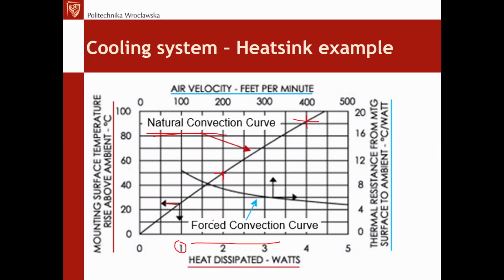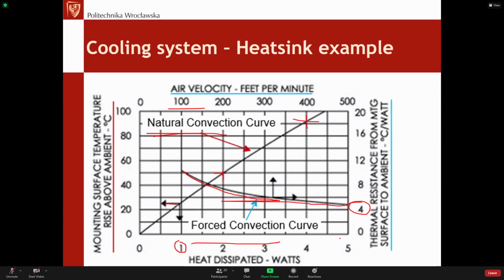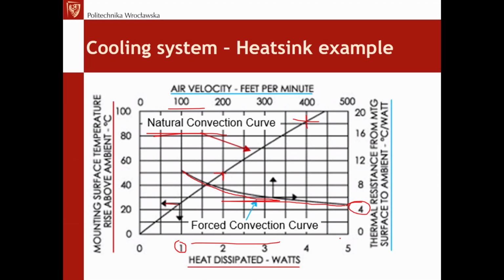In the case of forced convection, adding a certain airflow actually reduces the thermal resistance. Reducing thermal resistance means that if you increase the airflow, with constant power loss, the temperature of the case and the junction will drop. So the larger the airflow and the lower the thermal resistance, the lower the temperature of the junction and of the case itself, which is what we want.